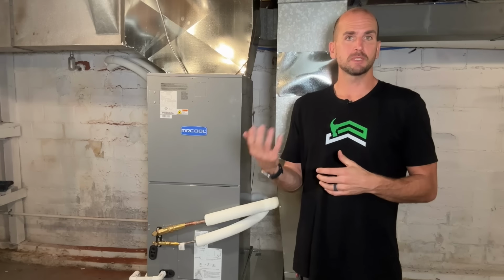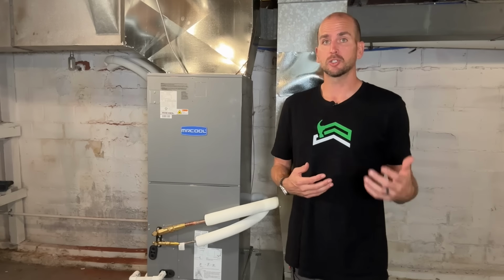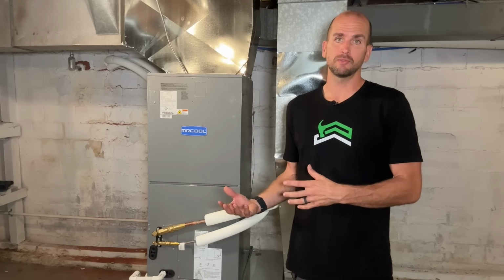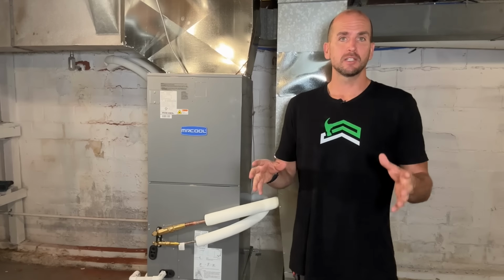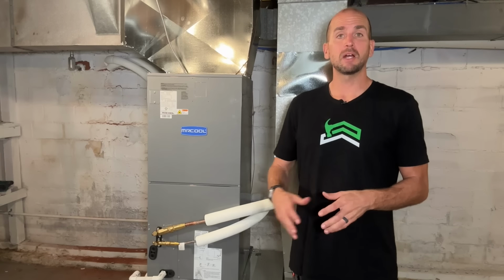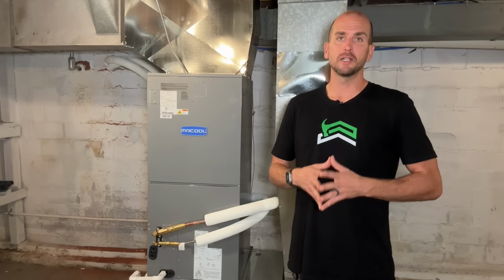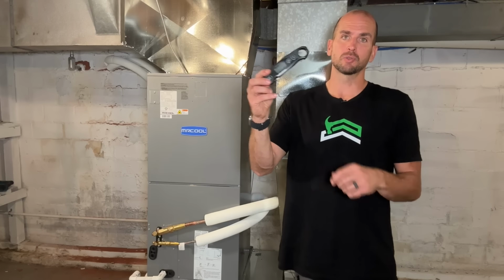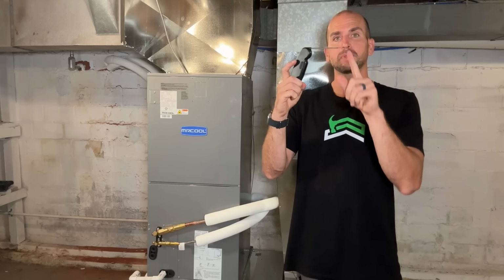Once that's on, your thermostat should be activated and you can turn that to cooling to start testing out the cooling functionality of this heat pump. It'll take a little time. You'll hear some refrigerant flowing around and the outdoor unit will turn on. But what I like to do is use a little grill thermometer here and I just place this in the vents.